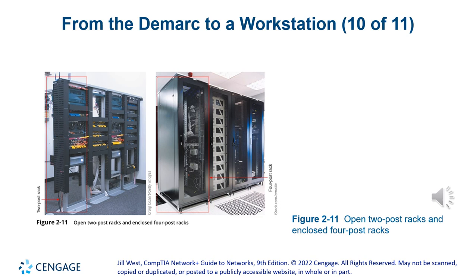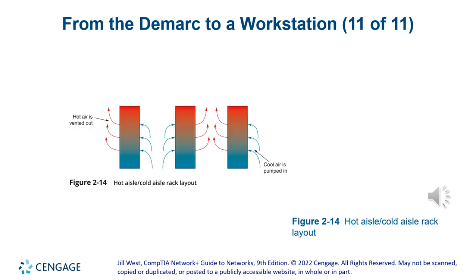So the equipment will come in with fans, and the fans will try to suck in the air to cool the equipment. So if you have air at the front of the rack, it will suck in all that cold air to cool the equipment, and it will push it to the back. So for those cabinets that are right next to each other, cooling is very difficult. Most likely what happens between, like, four cabinets next to each other is that you remove the panels in the middle, so all those panels are completely open across. And then you just put the end panels at the edges, at the ends, right? But the cooling still has to go from front to back, and we'll see that on the next slide.